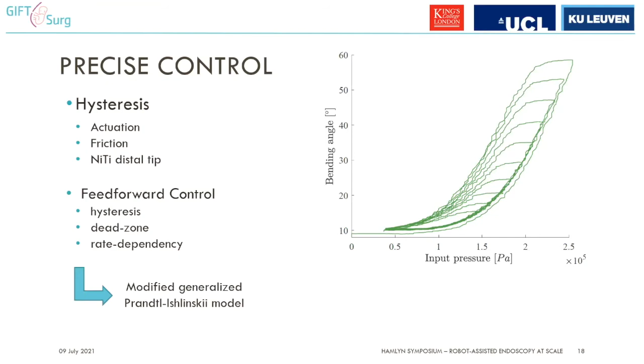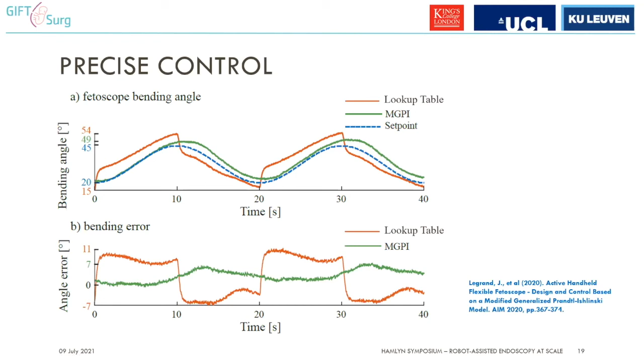modified generalized Prandtl-Ishlinsky model. You can look it up in this paper, showing that it is possible to get a relatively smooth motion if you're applying such a feed-forward controller. Here in blue, you see a reference signal. The green is the modified generalized Prandtl-Ishlinsky response, which is much smoother than, for example, a lookup table that we also implemented. It's not perfect, but a surgeon is in the loop, so he can compensate for that. Advantage is he doesn't see any jerky motion upon velocity reversal, and this becomes a workable system.